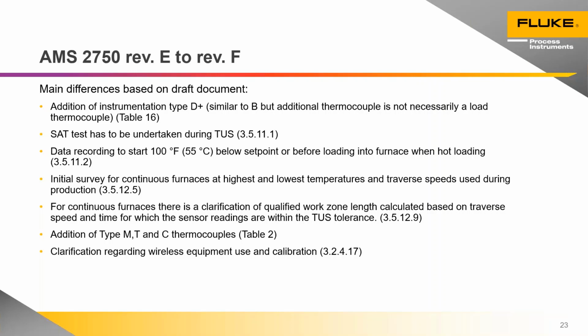For continuous furnaces, there's been a clarification around work zone length or qualified work zone length. I would suggest, and we've put the clause number in there, that anyone with a continuous furnace needs to read that in more detail. To go through it here, we would double the time needed for this webinar. There's been an addition of some new thermocouple tables. That's not an issue for us.